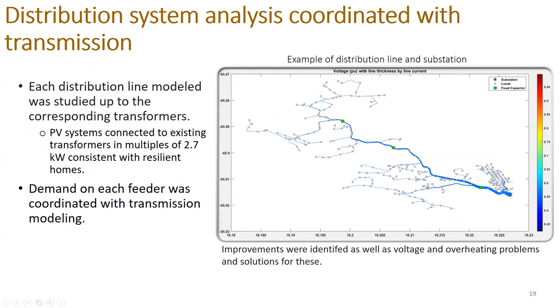So how did we go about that? Well, we looked at each and every feeder and we did an allocation of the PV and battery systems onto each feeder geospatially, based on the location of the distribution transformers. The GIS model had a geospatial representation of the size and location of essentially every distribution-level transformer on the PREPA distribution system. So the logic went like this: we know that where there is a distribution transformer, there is likely to be a load of some form or fashion.